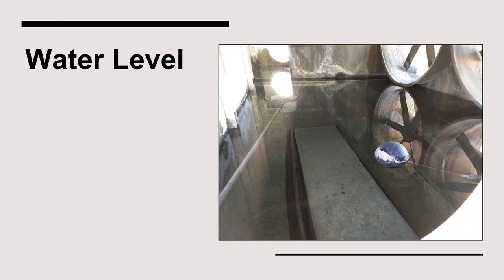The bottom of a condenser is typically filled with water which is pumped to the top of the condenser where it is sprayed over the tube bundle. If the water level drops too low in the condenser, it will not have enough to operate properly and condense the ammonia. Each condenser sump is equipped with a float that controls the water level. If this float gets stuck, it would cause the sump to dry out or overfill. In colder climates, condensers can be equipped with a remote sump located indoors to prevent freezing of water.